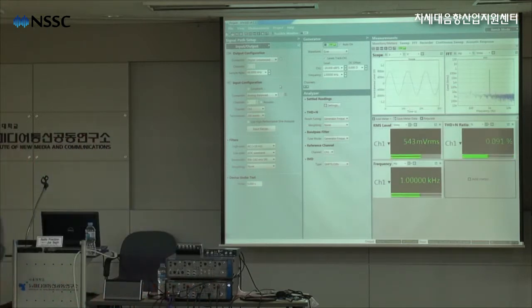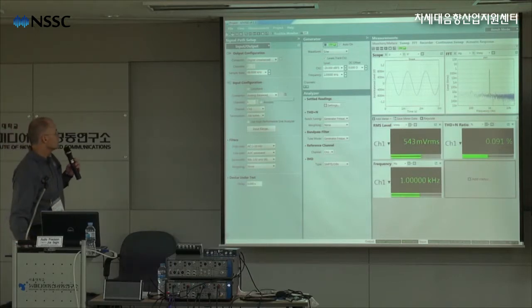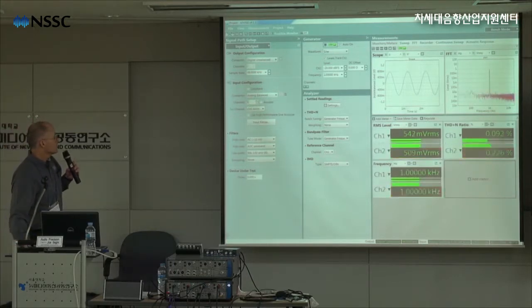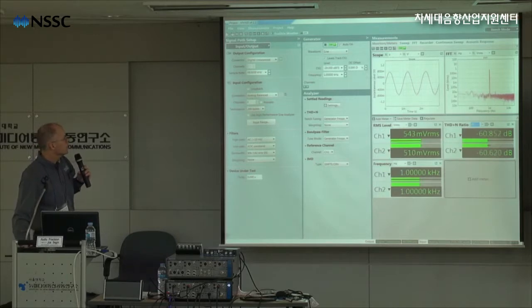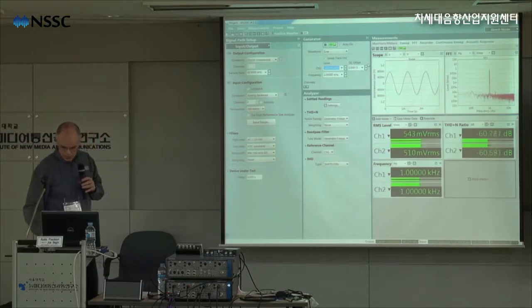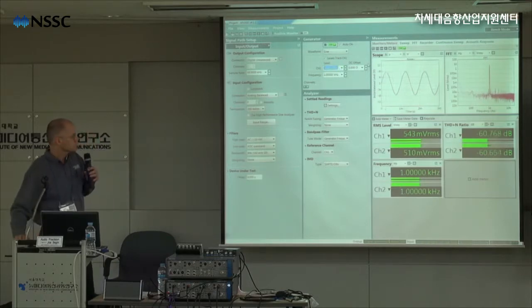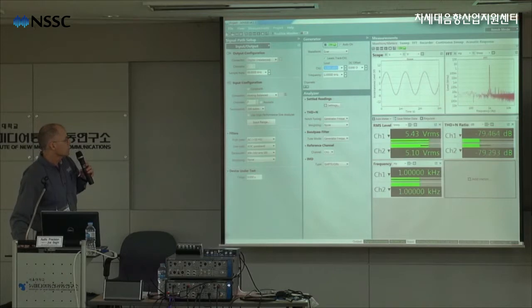Okay, so earlier I changed the input to one channel. So we want to measure two channels. Here we're looking at the THD plus N ratio in percent. I'll switch it over to dB. And we want to set the output to 0 dBFS, or full scale. The analog level measured is 5.42 volts RMS on channel 1 and 5.1 volts on channel 2.